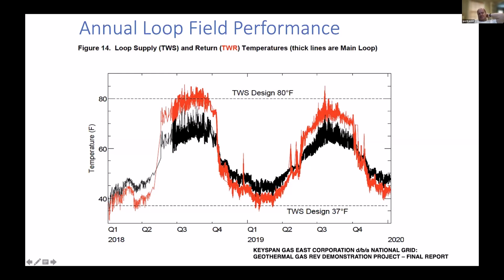And then the temperature goes down again, where the loop field is extracting heat from the ground. And 1 year later, it's doing the same thing. It peaks again around 75 degrees. And in the winter, it draws the temperature down again. And you have all those little events here in between where the loop field is reacting to input and output. You do have sometimes cold spans. You have warm weather. And this is all reflected in here.